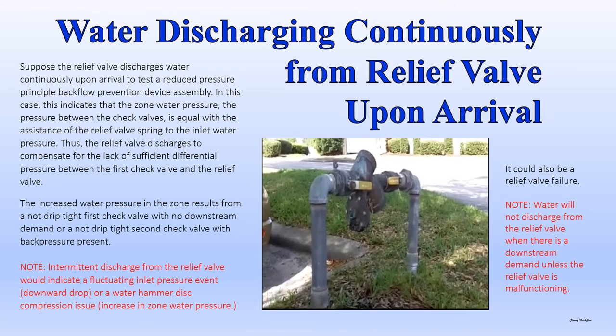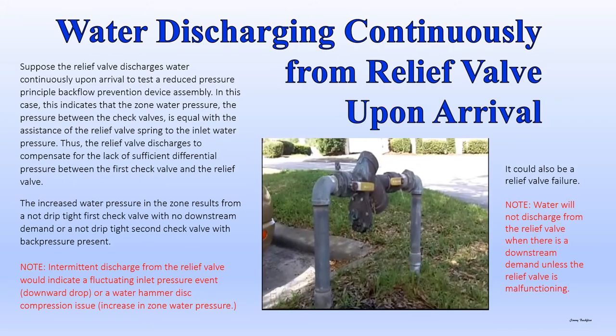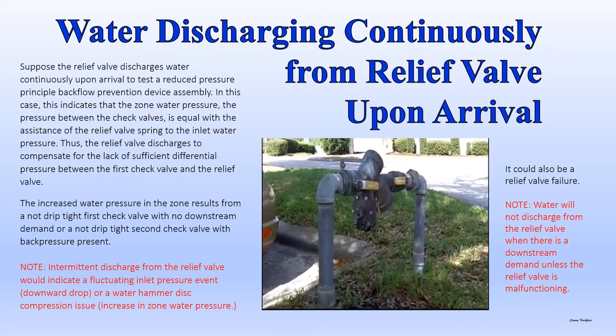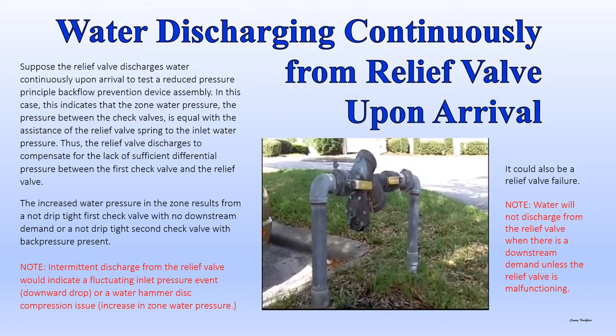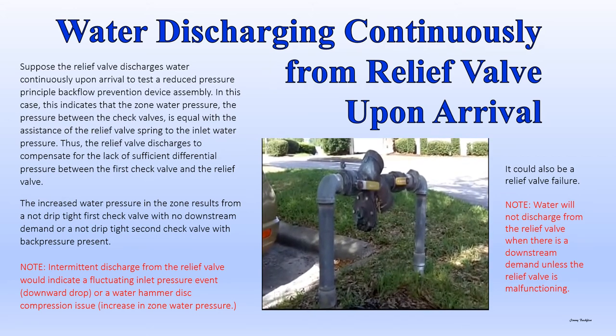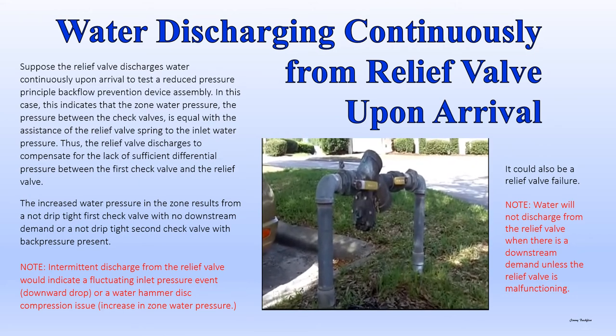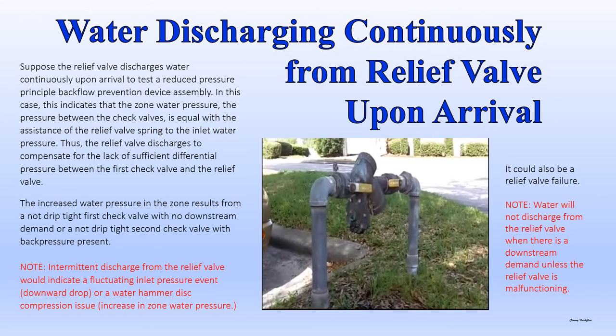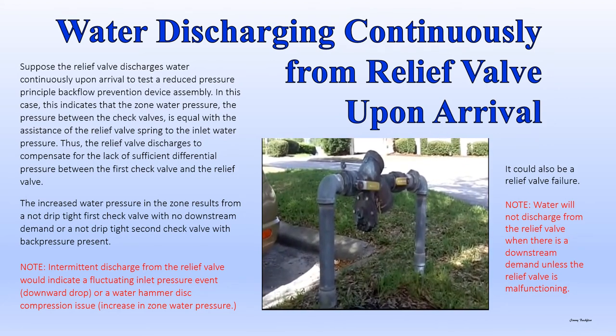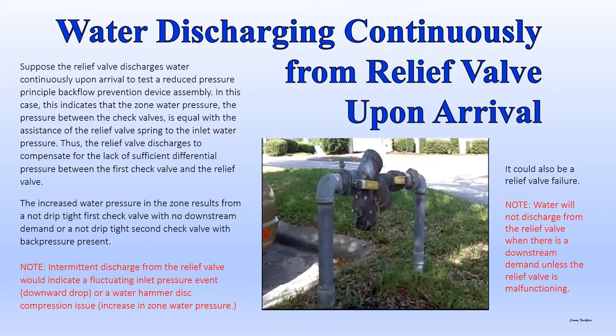Water discharging continuously from the relief valve upon arrival. Suppose the relief valve discharges water continuously upon arrival. This indicates that the zone water pressure between the check valves is equal, with the assistance of the relief valve spring, to the inlet water pressure. The relief valve discharges to compensate for the lack of sufficient differential pressure. The increased water pressure in the zone results from either a not-drip-tight first check valve with no downstream demand, or a not-drip-tight second check valve with back pressure present. Intermittent discharge would indicate a fluctuating inlet pressure or a water hammer disc compression issue. It could also be a relief valve failure. Water will not discharge from the relief valve when there is a downstream demand unless the relief valve is malfunctioning.